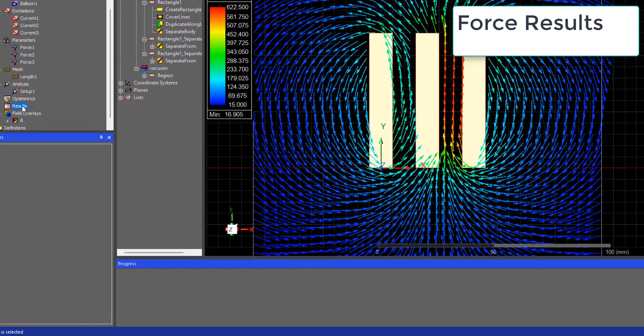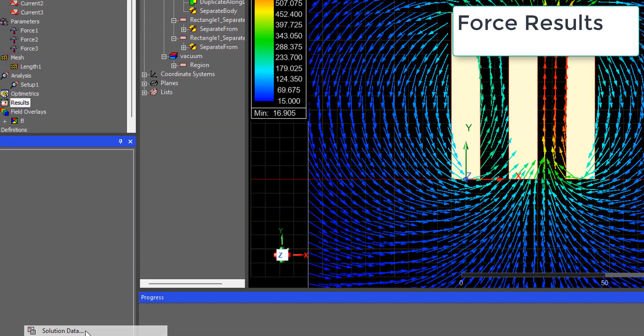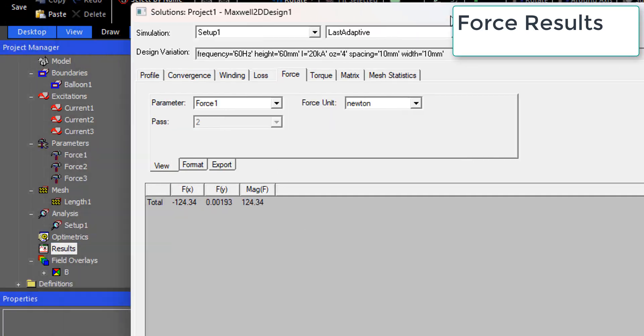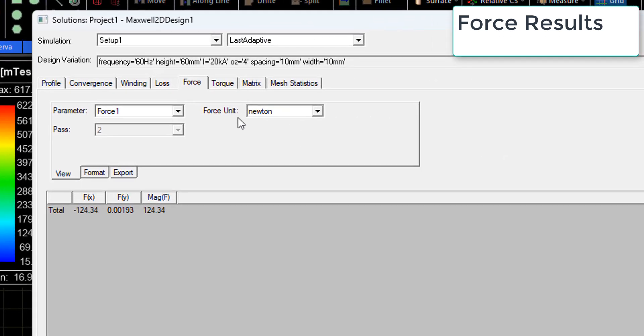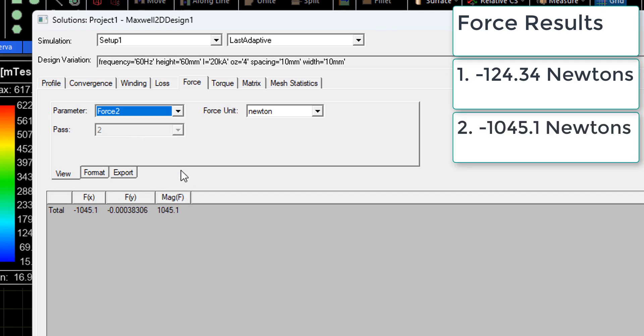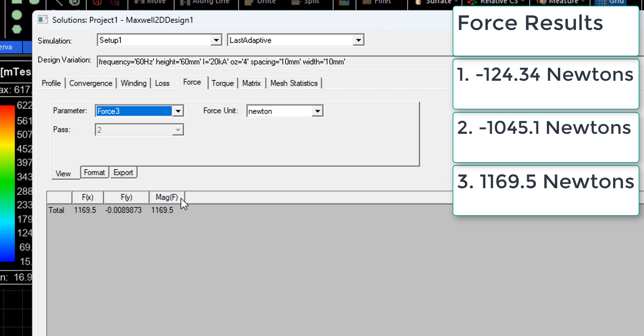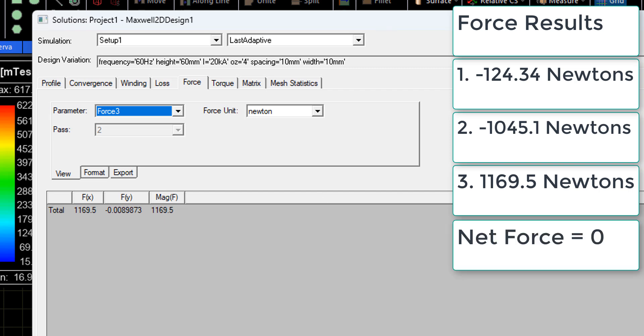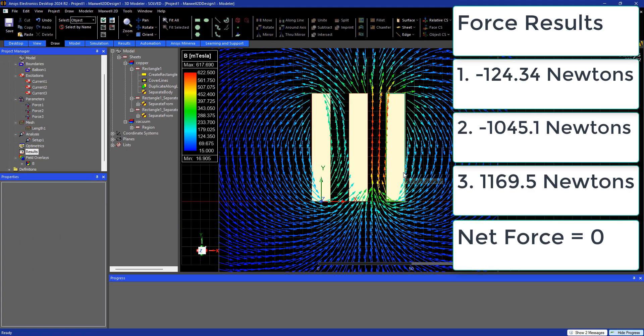Now let's take a look at the force results. We go to Results > Solution Data and we can see the force for each of the busbars individually. The force is applied mostly in the x-axis. Busbar one has 124 Newtons in one direction, busbar two has 1045 Newtons, and busbar three has 1169.5 Newtons. If you sum all three, you will get something close to zero, which makes sense because the total force applied to the system is zero.